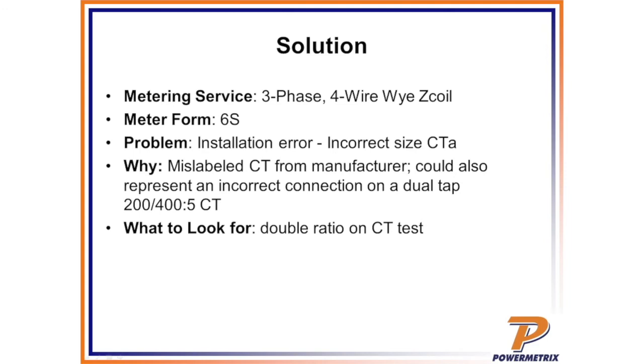So again, what John is referring to is when you're setting up the site in either a meter site manager or on the PowerMaster. In this case, you need to go in and select the transformer, the 400/5 or 200/5 CT in the site. Otherwise, we would give it a pass as long as the measurement was within specifications. So it may be a false positive.